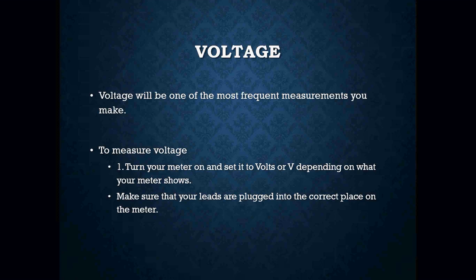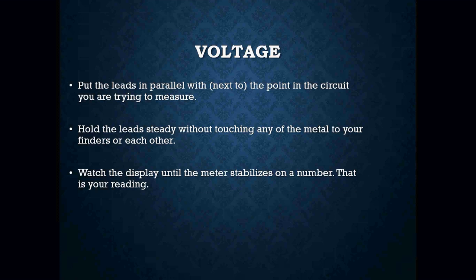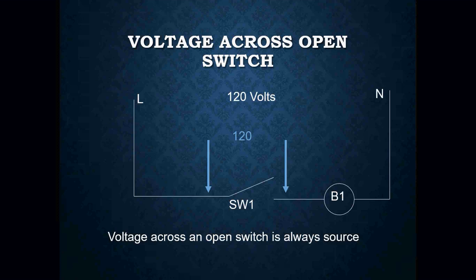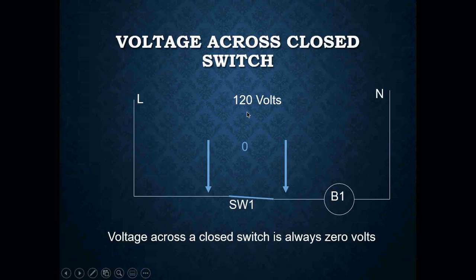Make sure that your leads and everything are plugged into the correct spaces on your meter. You're going to put the leads in parallel with, or next to, the point in the circuit you are trying to measure. Hold those leads steady without touching any other metal to your fingers or each other, and then watch the display on your meter to stabilize on the number, and then that's your voltage reading. So for voltage across an open switch, you will always read source voltage because we are now picking up that difference in potential. Remember, electricity always wants to follow the path of least resistance. In this case, with the switch open, the electricity will actually pass through the meter, and it will pick up that 120 volts.